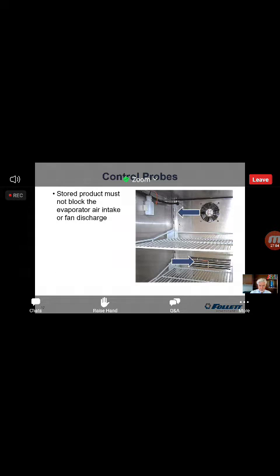So on the control probes, a couple of things. Number one, when you're putting product in there, we need to make sure that we don't block the airflow. These are forced air cooling units. Now that gives them fantastic recovery performance. They recover temperature very quickly after door openings, because we're forcing the air through that actual heat exchanger, that fin and tube evaporator that's behind that rear panel that you see right there. So we need to make sure we don't block any of that airflow.